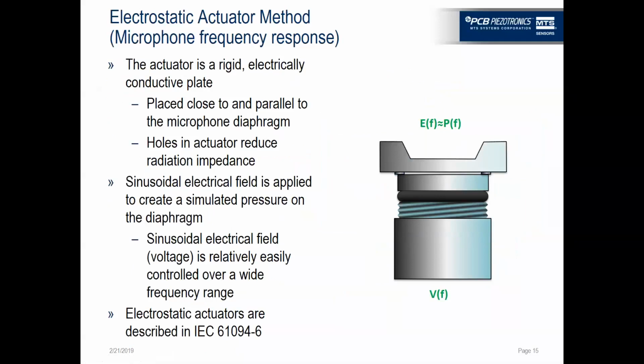I spoke about an electrostatic actuator before, and just here I want to go over what it does. I'm very fond of this term: an electrostatic actuator is a dumb piece of metal. It has no components other than a piece of metal and some insulative feet. And those feet that you can see in this drawing here are these little tiny parts that are separating the metal actuator from the microphone, so it can't complete the circuit. And there are holes perforating this here, and there's a gap here.